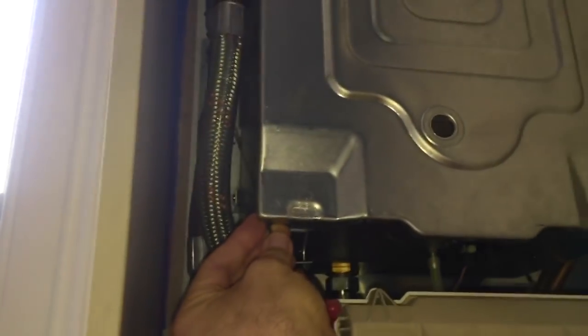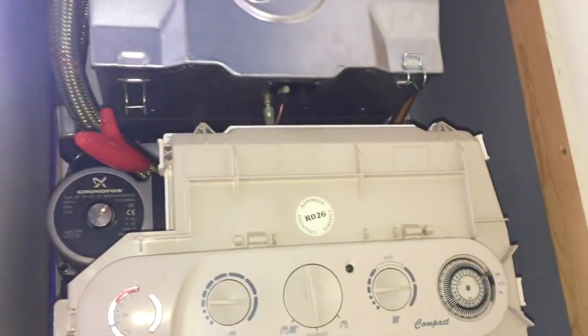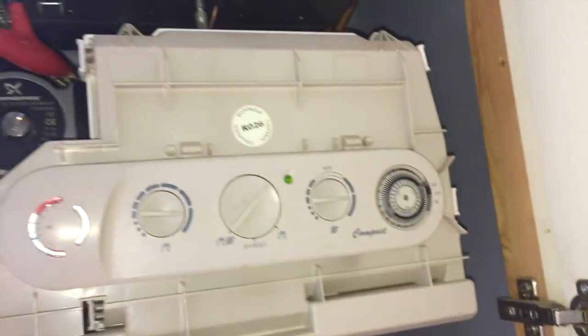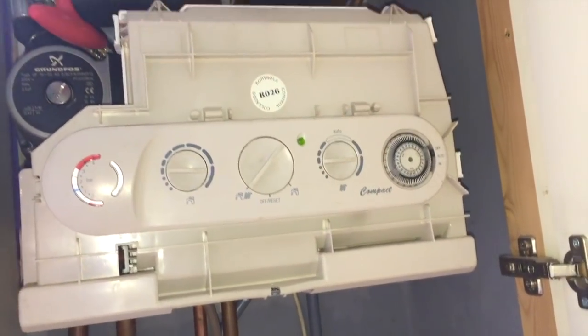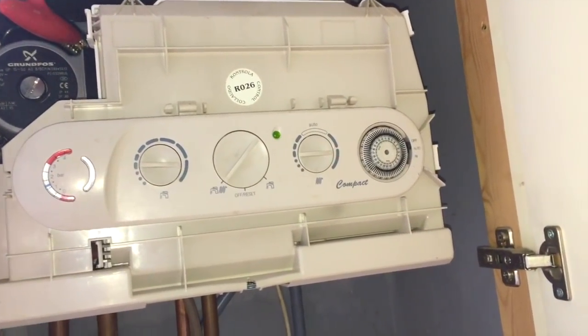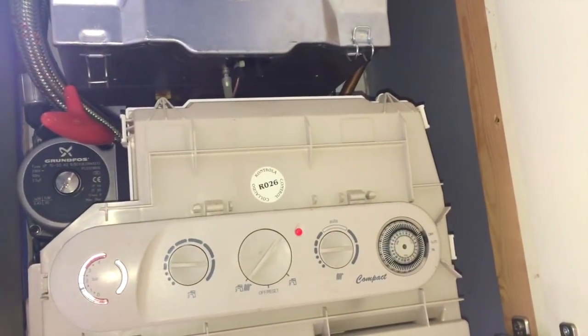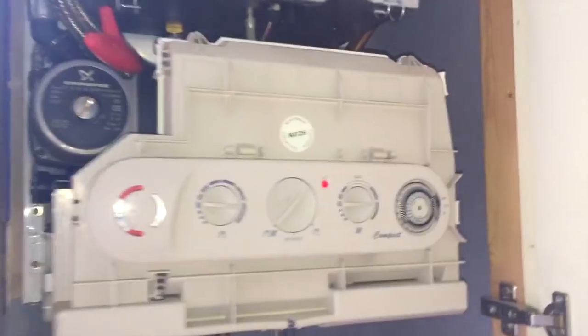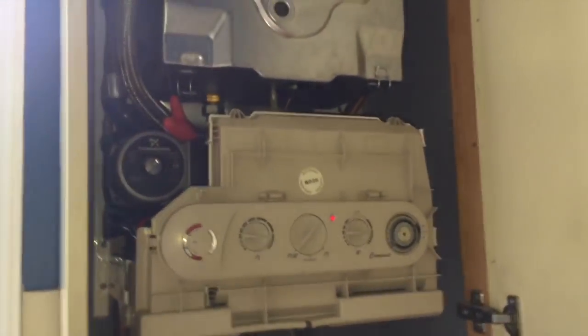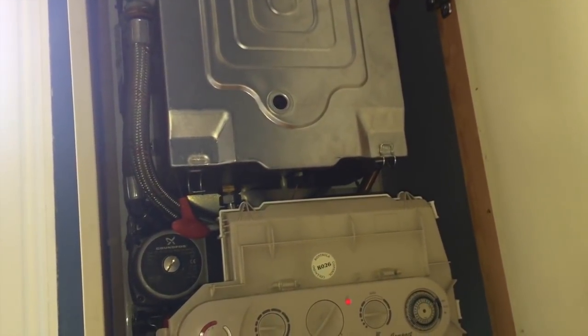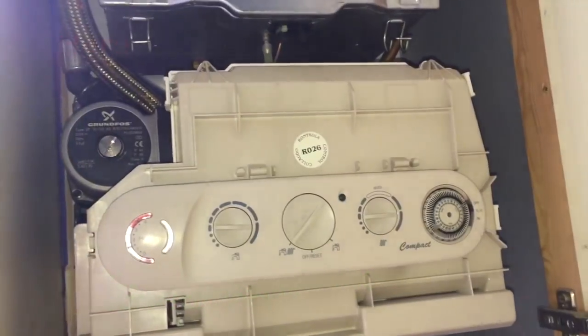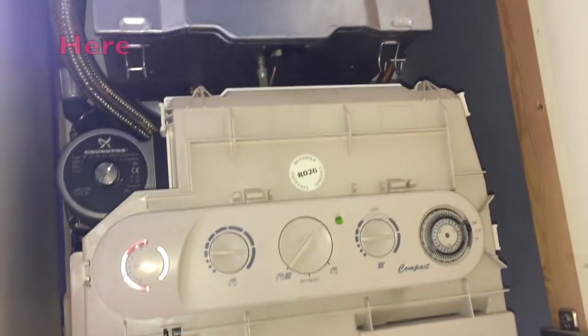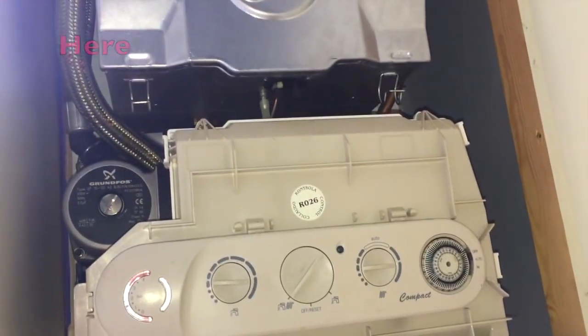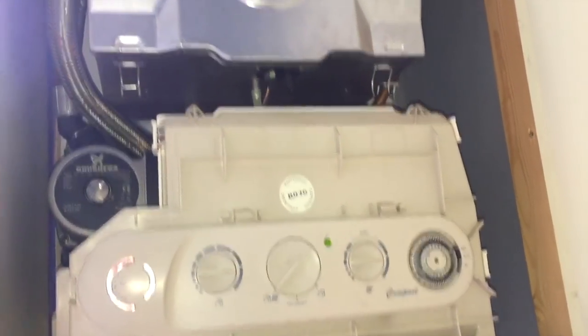probably just crack this open a little bit, like that. So look, that's just holding that ever so slightly open. Don't want this to run for too long to get too hot, or maybe not. And then, if that made the air pressure switch. Didn't appear to, so I can check it on the board to confirm whether it's making or breaking the air pressure switch. Okay, so just crack that open. Nothing.